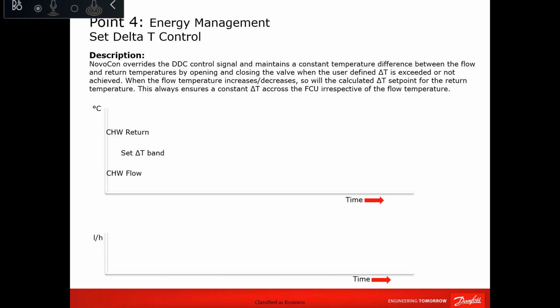So here is another way to do it, but in the last slide we saw the minimum delta T. Here's the set delta T. The difference is simple. When you control minimum delta T, the moment you achieve the minimum delta T, you will release the control back to the thermostat or the DDC controller or the BMS. So once the delta T is achieved, you will have the normal operation.